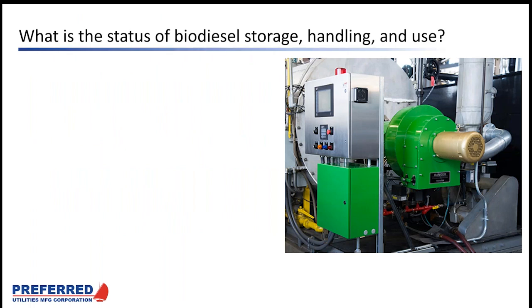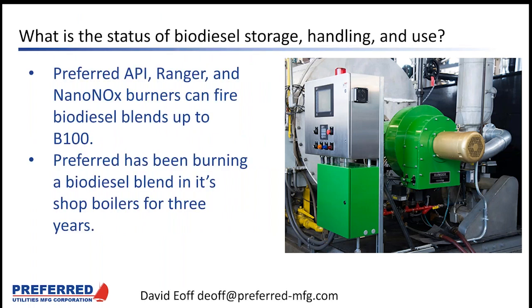With the burners, there are fewer components that need replacing for biodiesel. The concern is more about the combustion aspects of burning biodiesel than chemical compatibility. The BTU content and viscosity of biodiesel are a little different than ultra-low sulfur diesel, and this affects the sizing of the pumps, the fuel trains, and flow control valves. Also, the amount of air needed for clean combustion is a little different, so this needs to be taken into account with the fan sizing.